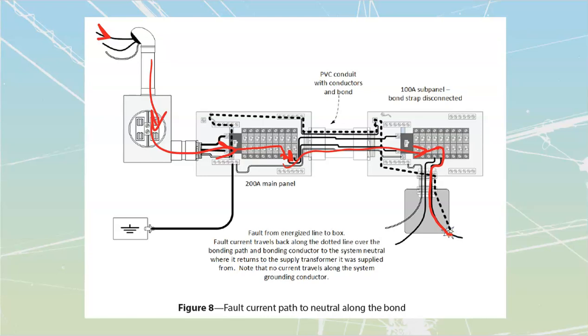What we will have then is a return current. The current's going to travel back along the box, up through the nipple, across the panel. The panel is going to be metallic. It is then going to go to the bonding lug inside of the panel, which has a bonding connector. There'll be a green connector run through this PVC. It says that there's a bond inside of there. So it's going to run back along the bond to the bond lugs inside of this panel, travel through the case of this panel, travel up the bond strap back to the neutral, and then travel from the neutral back up the neutral conductor and all the way through to my transformer.